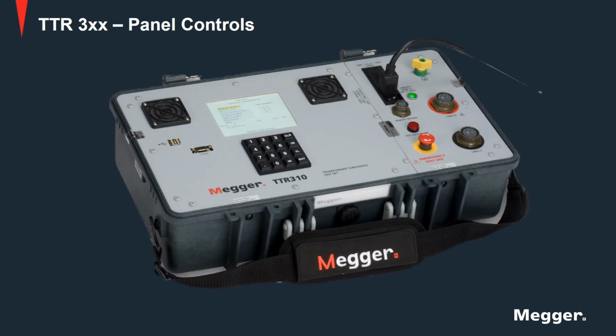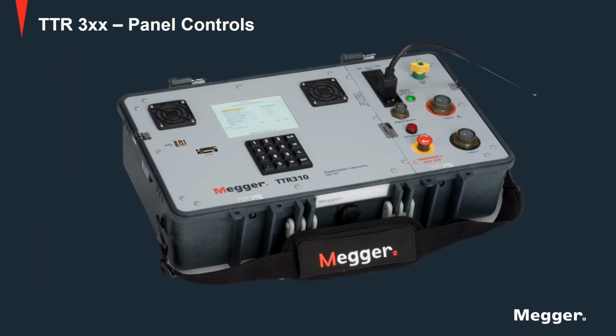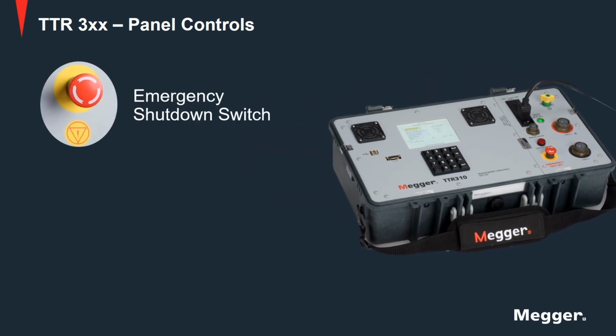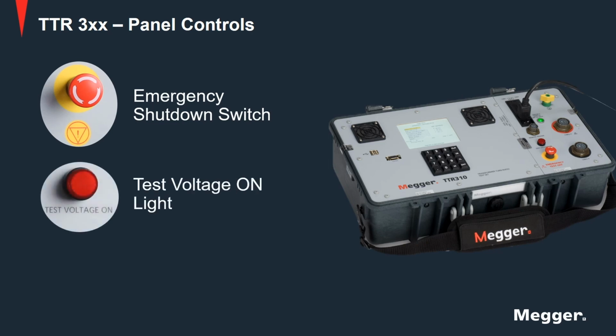Among other panel controls of the TTR300 include the emergency shutdown switch. This switch, when pushed, will disable the source power supply and automatically discharge the transformer. The instrument is continuously monitoring this switch in the event of an emergency. If the switch is engaged, testing cannot be initiated. Next, you have the test voltage on light. This is a red indicator lamp to show that test voltage is being supplied to the transformer under test.